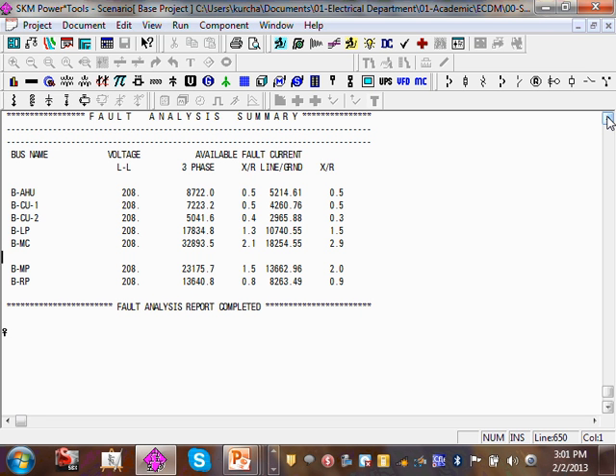So when I go size, guys, the short circuit right now for this circuit breaker here, the main, it has to be 30 in this case right here. It's going to be 23 or more, so it's going to be probably 35. I don't know if they make 25, 35, say 35,000 amp interrupting rate. So you have a short circuit, the circuit breaker says, I can handle it, open, and everybody's happy.